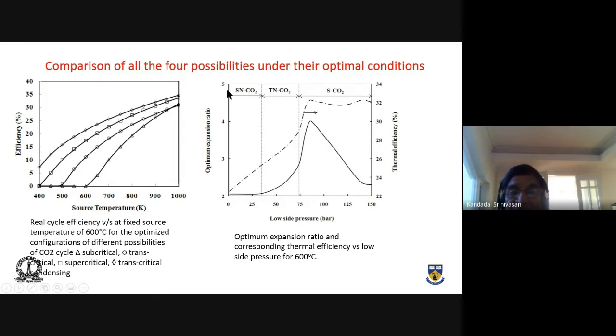So this is for the subcritical. N stands for non-condensing, subcritical non-condensing. This is the zone of operation because this is the low side pressure. Expansion ratios are very small. The critical pressure is about 77. So I can go maximum up to roughly about here. You can see that the minimum low side pressure I can go to is roughly about 30, 32 bar, because by the time I multiply by 2, the expansion ratio, I get nearly the critical pressure. But I want to operate the entire thing below the critical pressure. This is the transcritical non-condensing. But once you go beyond about 77 bar, it becomes supercritical.